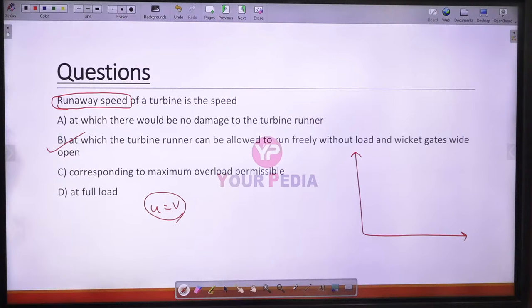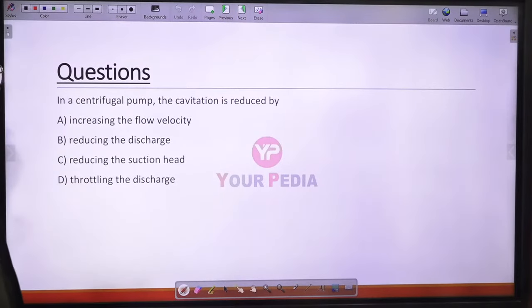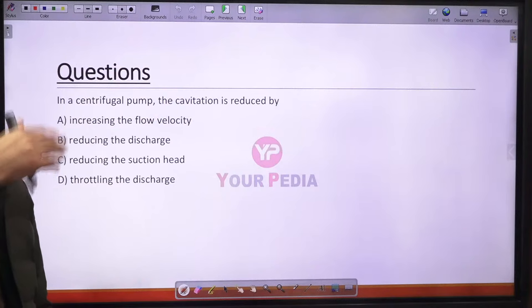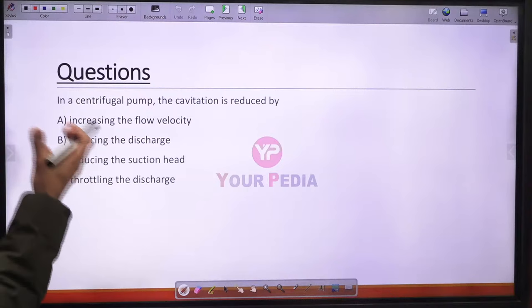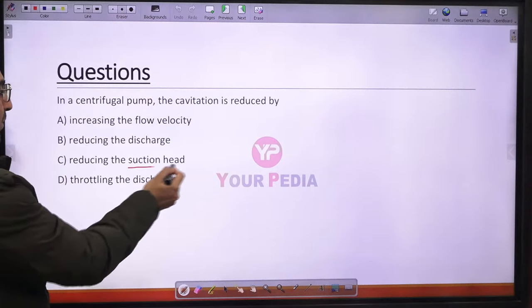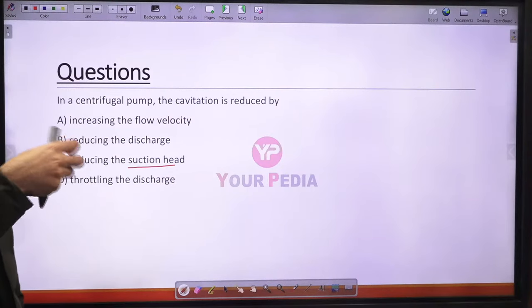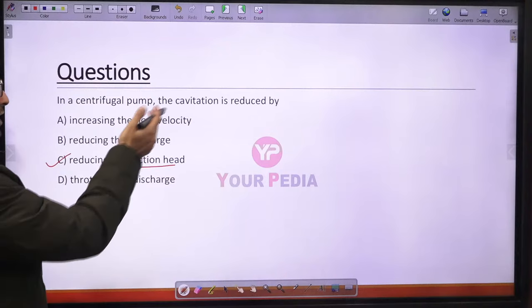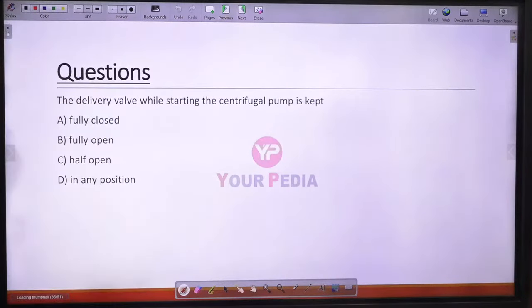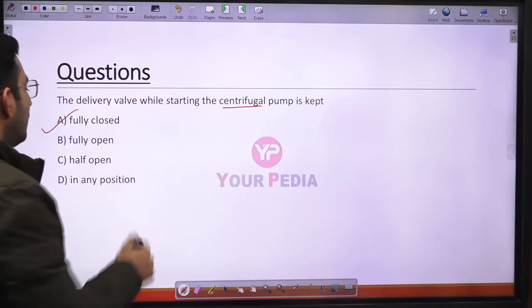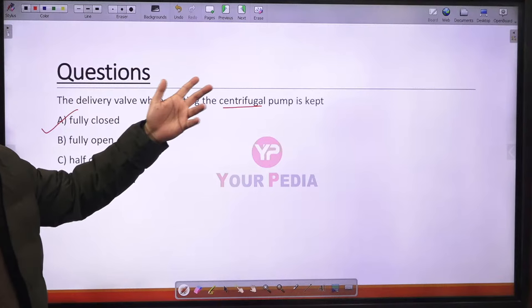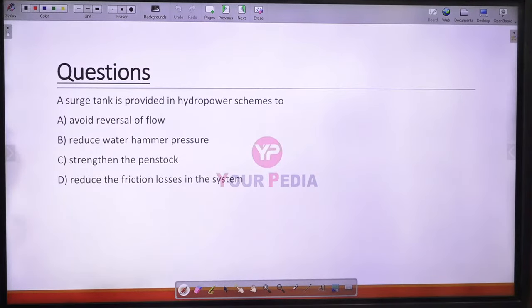Question 33: In a centrifugal pump, cavitation is reduced by reducing the suction head. Cavitation occurs at the pump inlet where pressure is very low. Reducing suction head prevents the inlet pressure from falling too low, reducing cavitation chances. Option C is correct. Question 34: When starting a centrifugal pump, the delivery valve must be fully closed to ensure pressure builds up properly before flow commences.